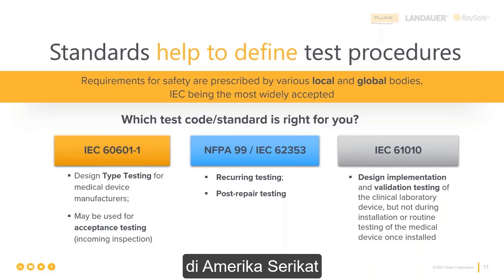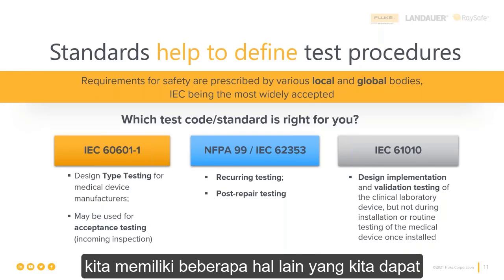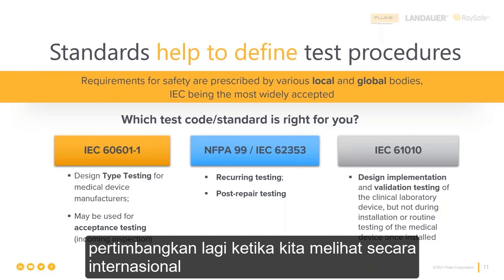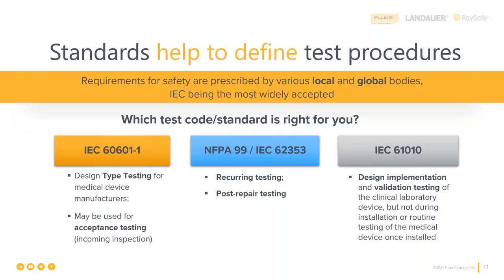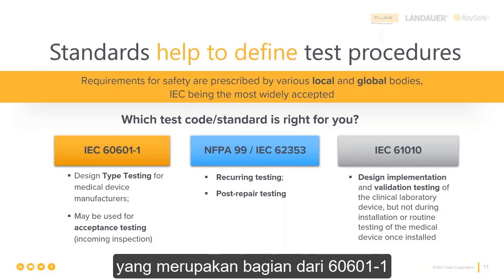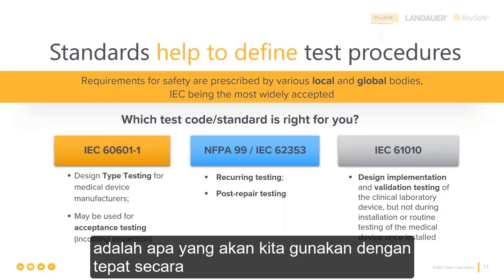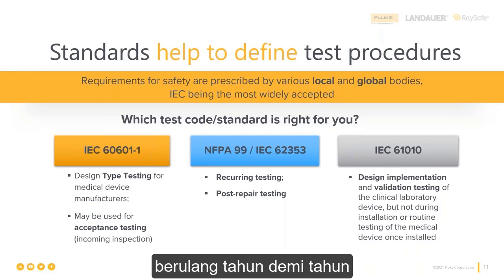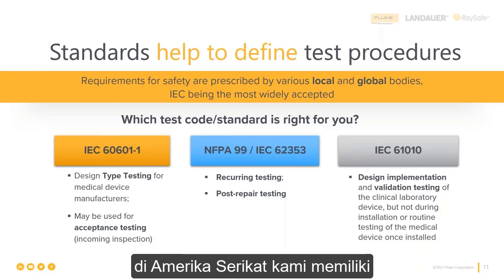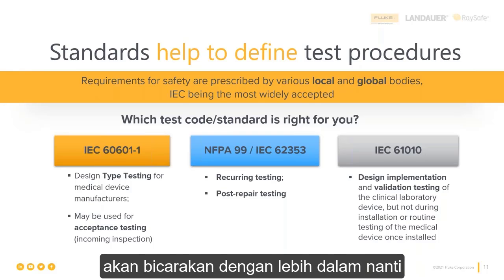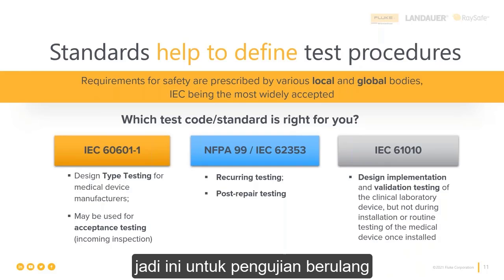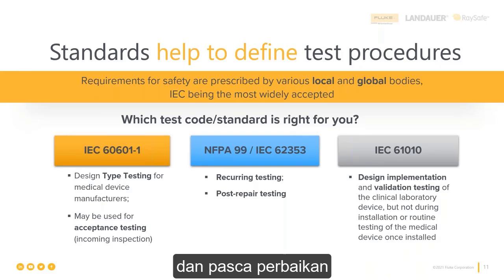In the United States, we have some other things that we can consider. Again, when we look internationally, the IEC 62353, which is a subset of the 60601-1, is what we would use appropriately, repeated year over year over year, for our scheduled maintenance electrical safety testing. In the United States, we have an electrical code, the NFPA 99, which we're going to talk about more later. So these are for recurring testing and post-repair.